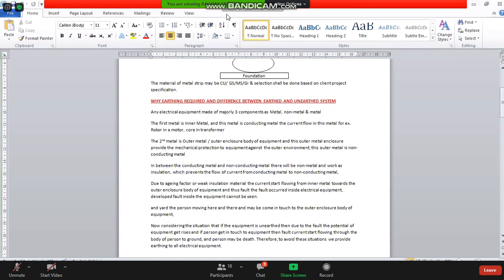Correct? Now, in the grounding part there is normal current flowing, and in the earthing part the fault current flows. In grounding, current is carried under normal conditions, and in earthing no current flows in a non-faulty condition. In the earthing, current will not flow. If there is any unbalance, then current will flow in the grounding. When the R, Y, B phases are a balanced system, current will not flow in the neutral. When an unbalanced system comes, then current will flow in the neutral.